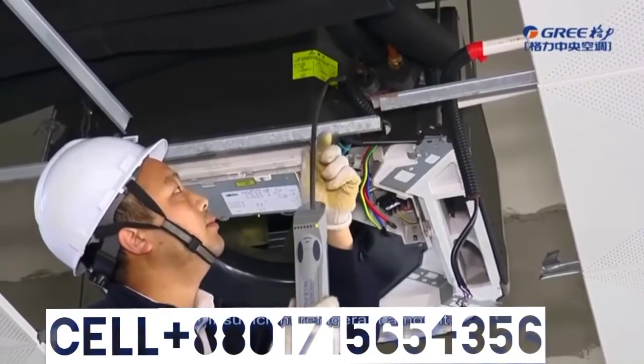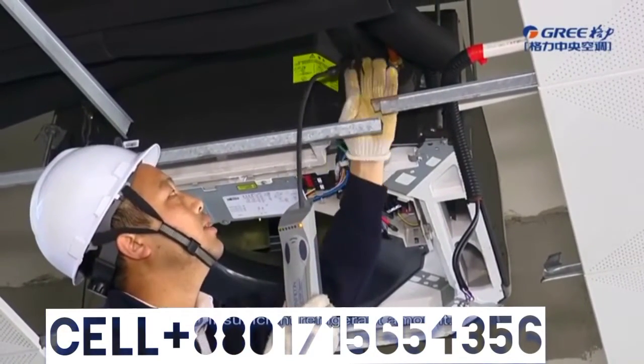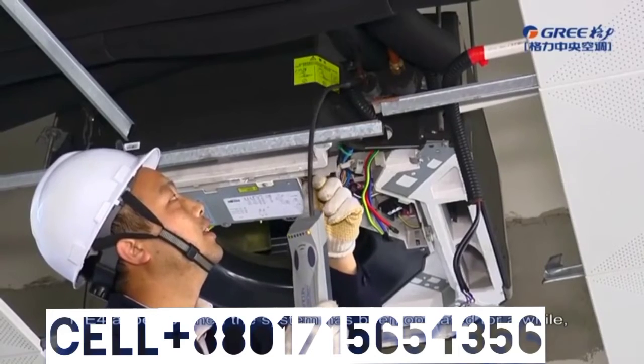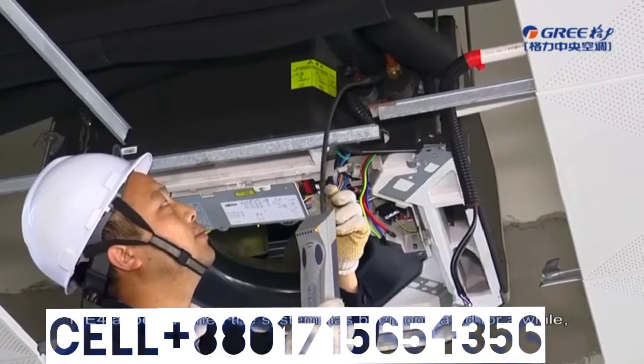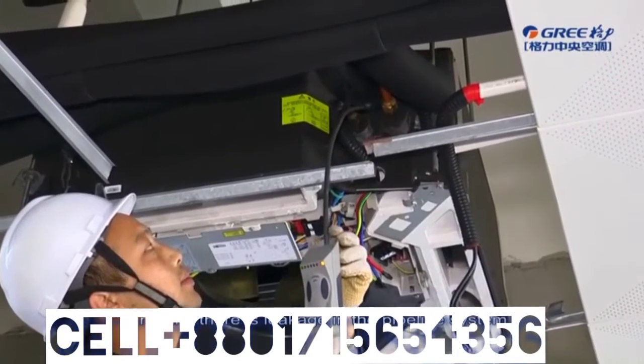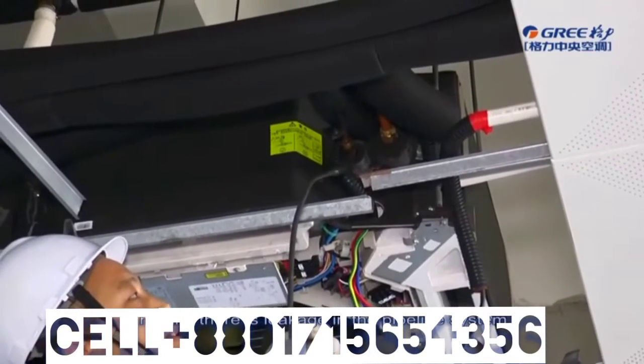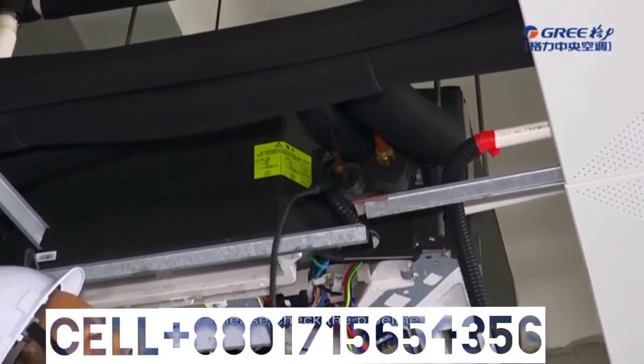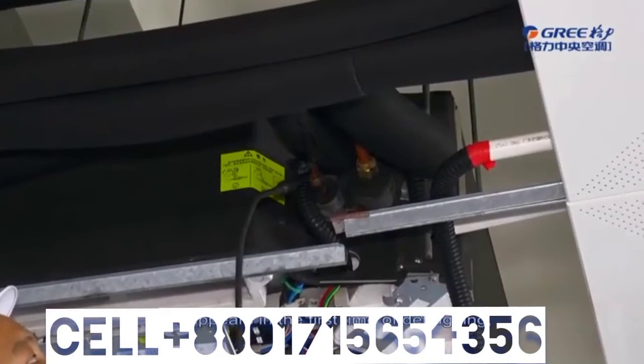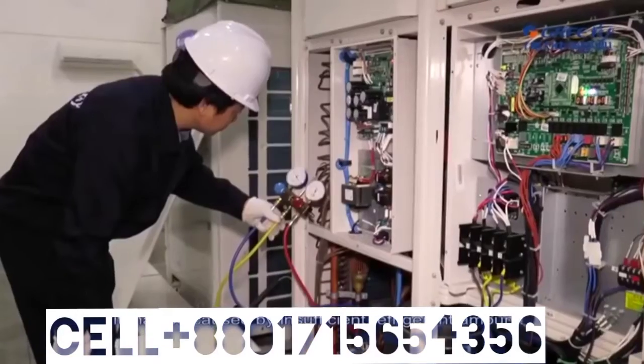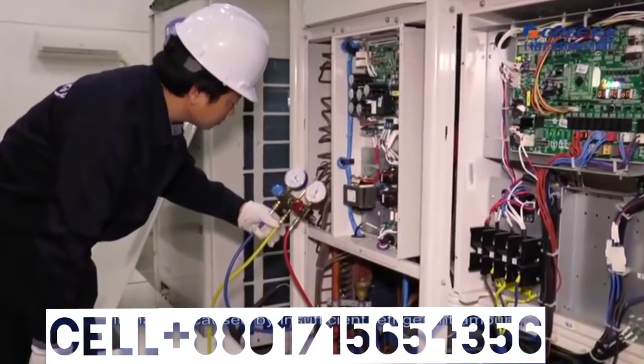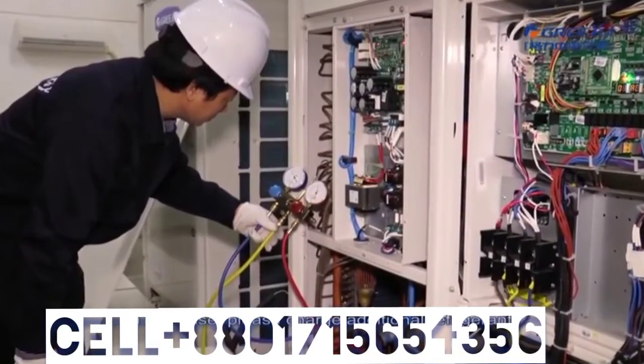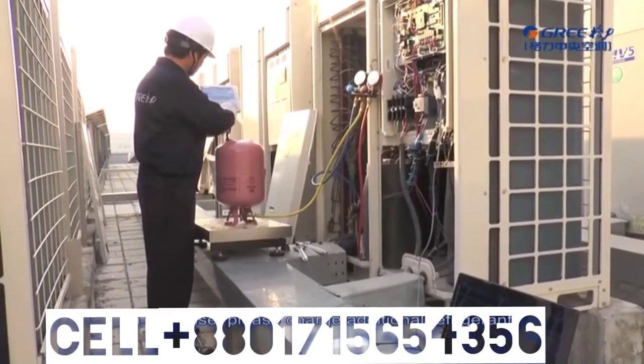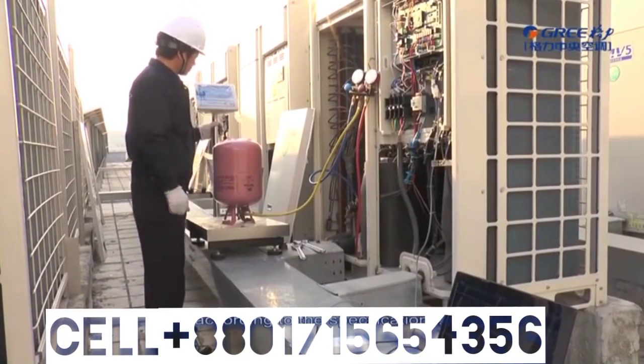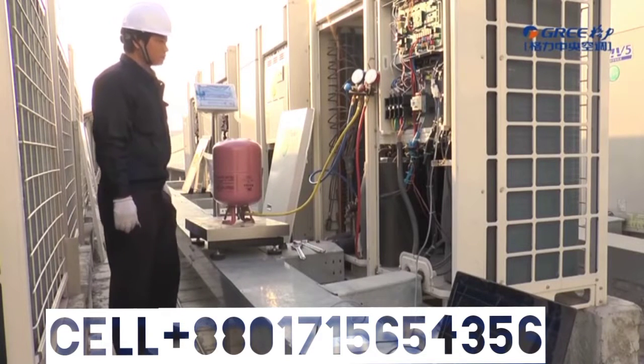Second, insufficient refrigerant amount. If E4 appears when the system has been operated for a while, it means there is leakage in the pipeline system. Please check the pipeline. If E4 appears in the first time of debugging, it may be caused by insufficient refrigerant amount. In this case, please charge additional refrigerant according to the specifications.